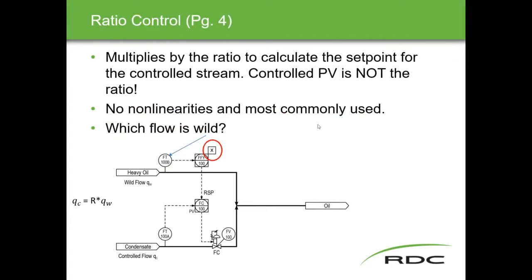Ratio multiplies by a ratio in order to calculate the set point for the controlled stream. The controlled process variable is not the ratio. So the controlled process variable, what we got coming out, is not the ratio. At any rate, the terms that we're going to deal with are wild flow, in this case the heavy oil, and controlled flow, in this case the condensate.